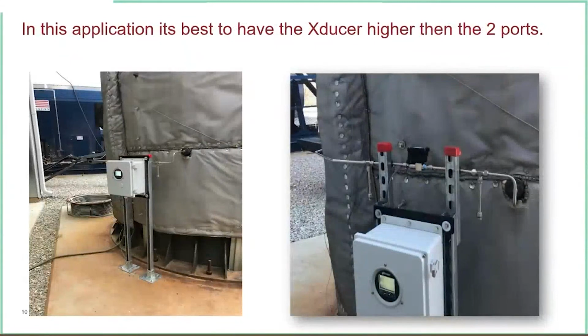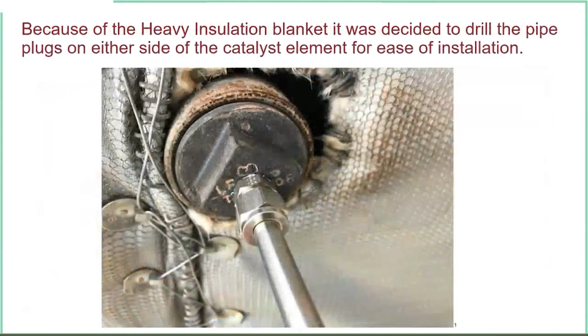And then this one here, with the insulation blanket completely mounted around that very large ground-based catalyst, it was going to be tough to get to either side. So to make life easy, the distributor did drill and tap the pipe plugs to take our 3/8-inch tubing over to the DP transducer. So that made life a lot easier.